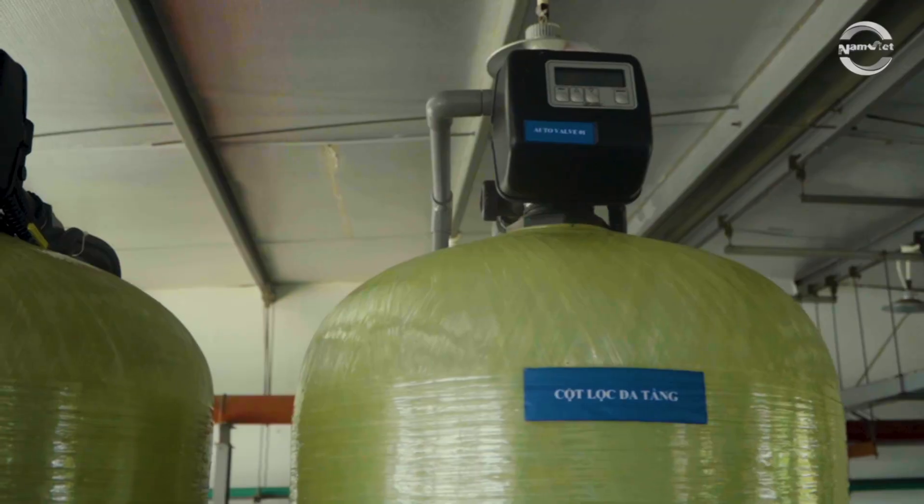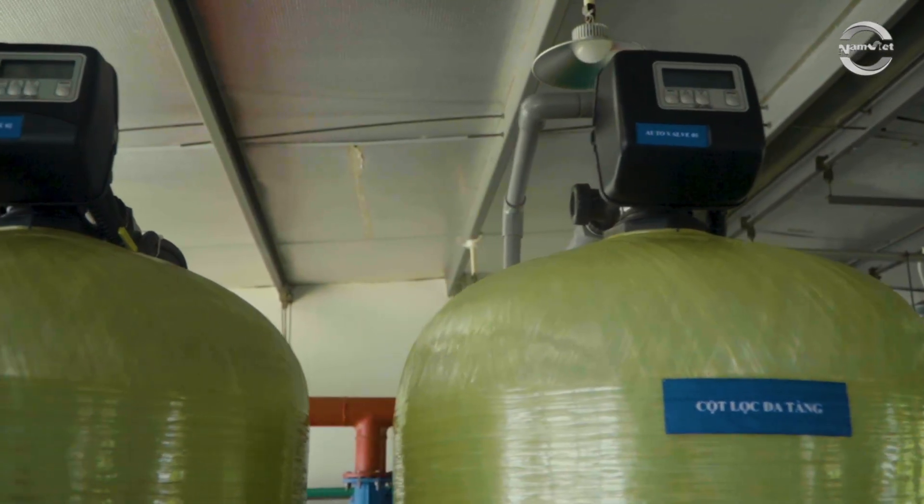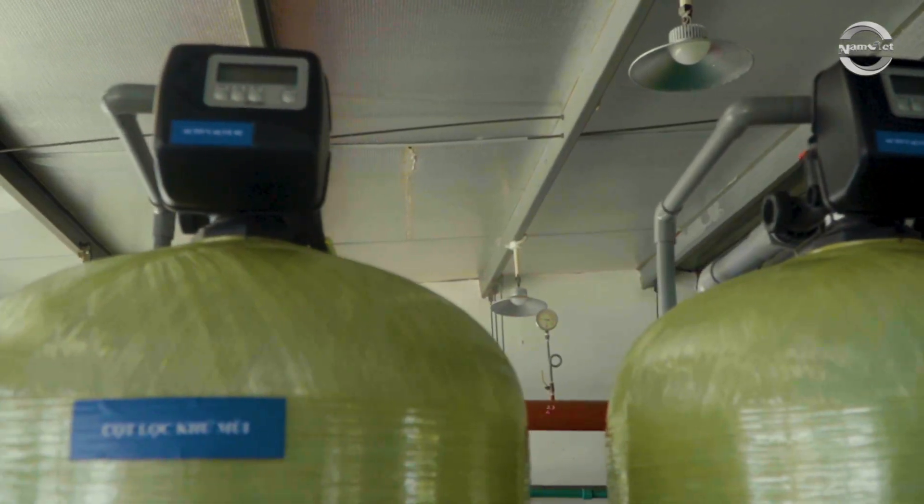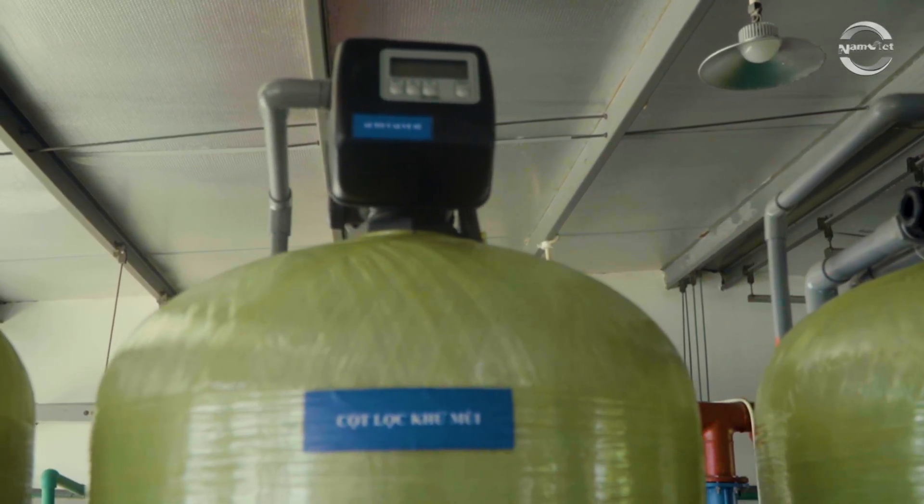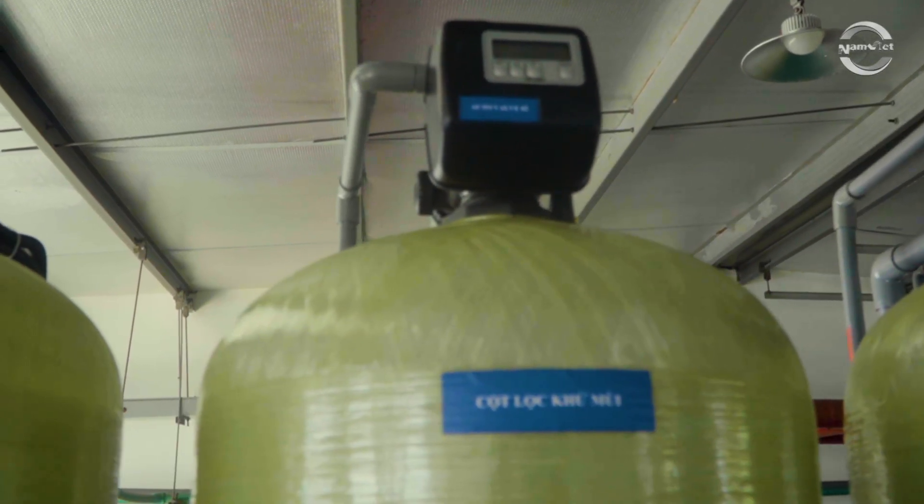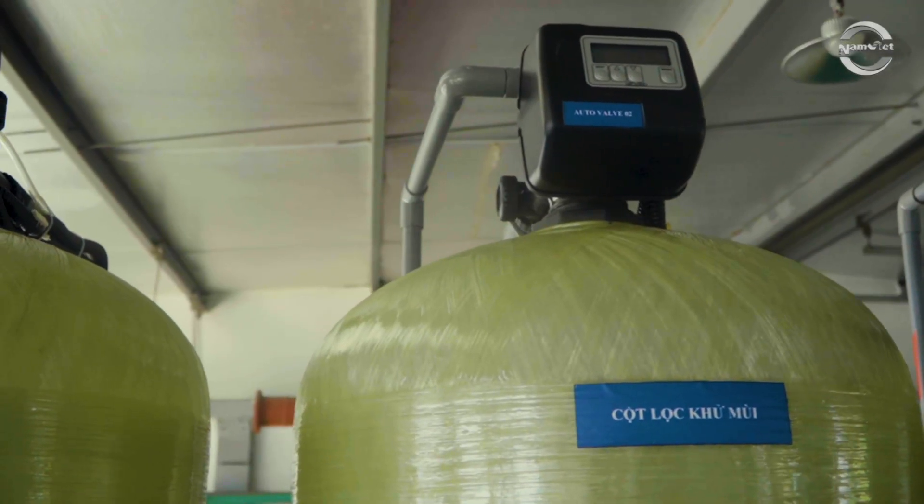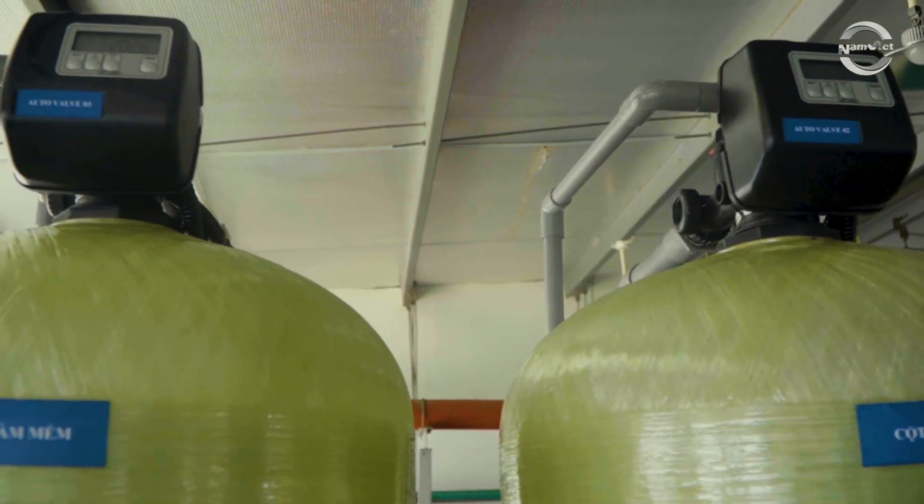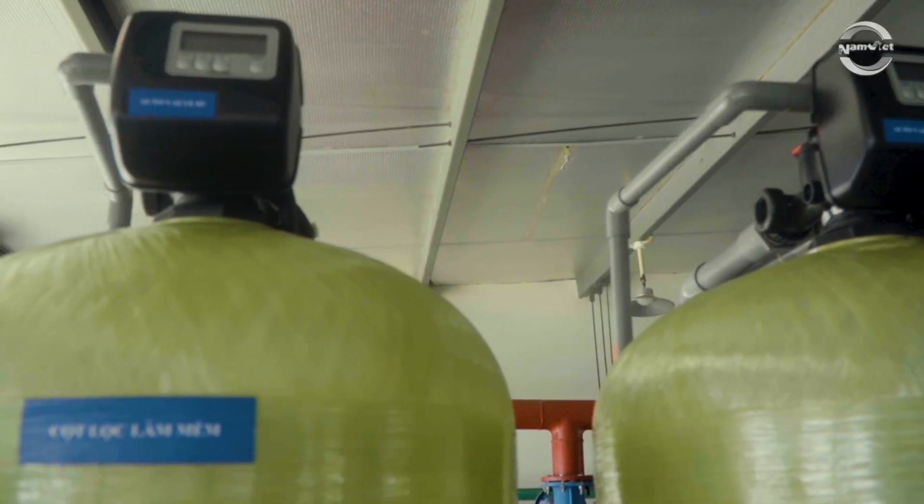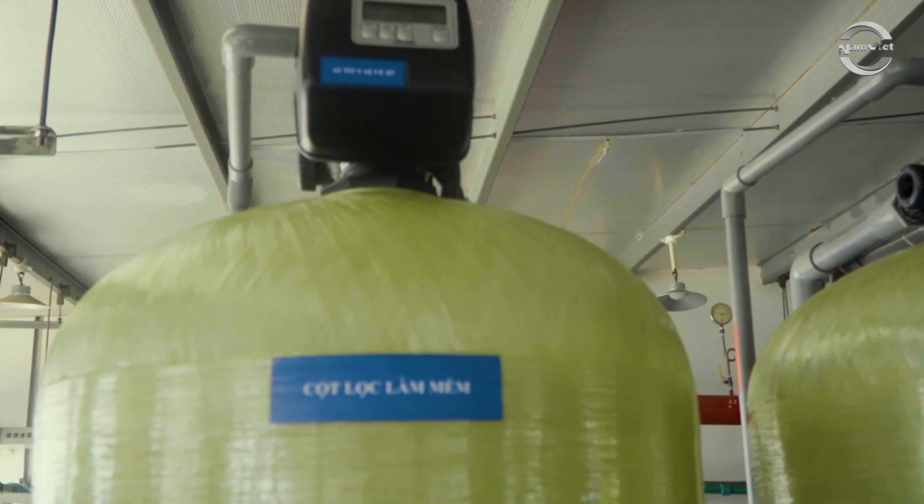The multi-layer filter column removes suspended solids and remaining turbidity from the water source, reducing sediment. The activated carbon column helps deodorize the water by absorbing organic matter, and protects the RO membrane from the oxidative effects of residual chlorine. The softening column removes calcium and magnesium ions to reduce inorganic scaling within the RO system.